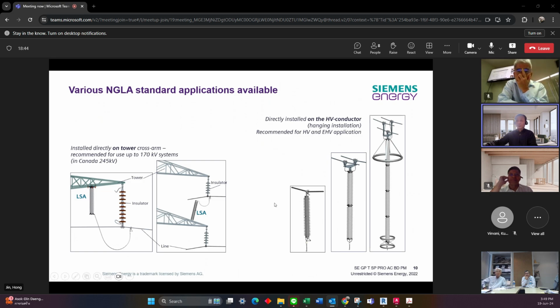So on this page, you can see different installation places of the non-gapped surge arrestor on the transmission line. For the voltage level below 170 kV, in Canada, we have also delivered for the 245 kV. The surge arrestor can be standing on the cross arm or hanging below the cross arm. Yeah? And another side will be connected to the transmission line. And for the extra high voltage, more than 300 kilovolt, the surge arrestor should be hanging on the transmission line.